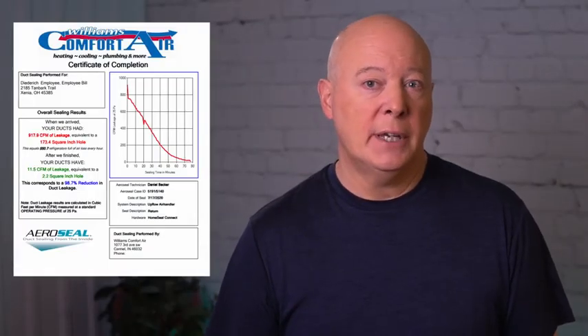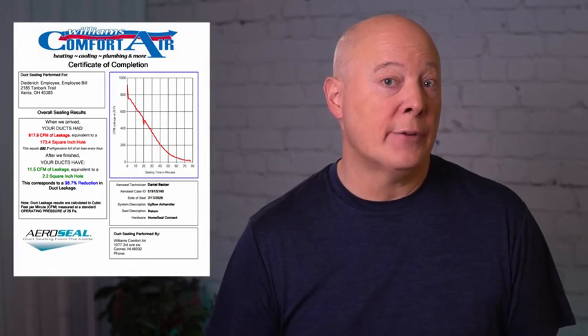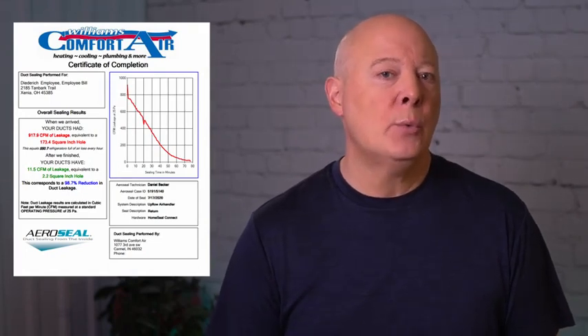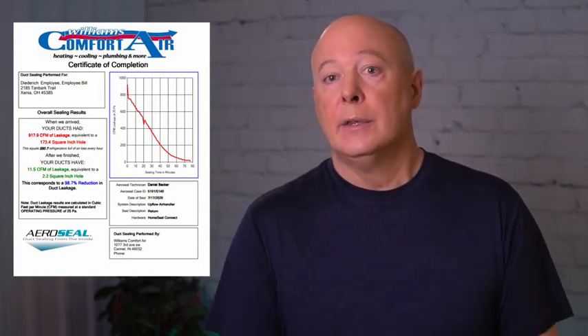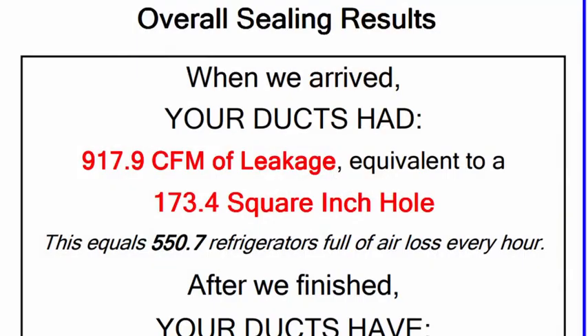Now, AeroSeal can usually seal these leaks, the smallish ones, since they are under the recommended 5/8 of an inch across. And it can seal larger gaps when the injection is let to continue longer. This return side seal certificate is a good example of a very successful seal on a 5-ton system in a 10-year-old Midwestern basement style house. The pre-seal test measured 918 CFMs of return leakage, equal to a 173 square inch hole. That's a lot of leakage, yet is quite typical for this kind of layout.